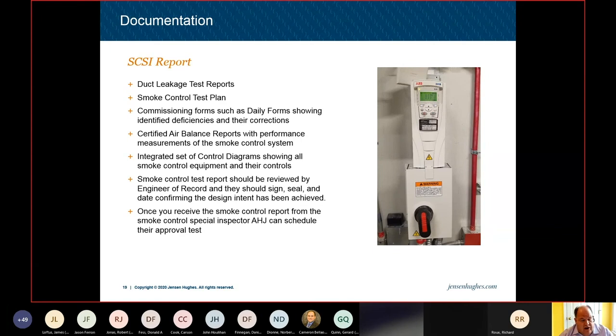And then there's also a requirement to have an integrated set of control diagrams showing all the smoke control equipment and its controls. Now, the code tells you that you need to provide it, but it doesn't tell you how best to go about it. So whether the fire alarm system is controlling the smoke control system, or it's just an input into a BMS system that's going to turn the smoke control system on, generally what I recommend is to take a good set of your fire alarm drawings, shop drawings, or as-builts, and use that as the starting point for your control diagrams. It's going to show you all the devices initiating the smoke control system, whether that's the smoke detectors, sprinkler water flow switches, in some cases manual pull stations, and all of those things are shown on the drawing.